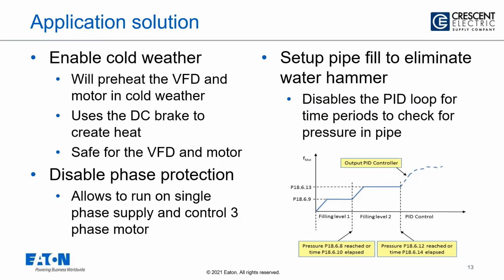And we talked about single phase input application. Most of the irrigation customers do not have 3-phase. No issues. We can connect a single phase to our 3-phase drives, derate them, and then control a 3-phase motor. So we have that phase loss protection disable function available for such applications.